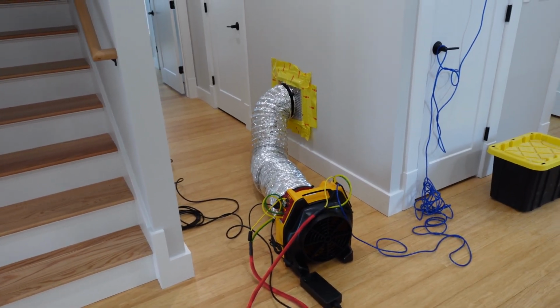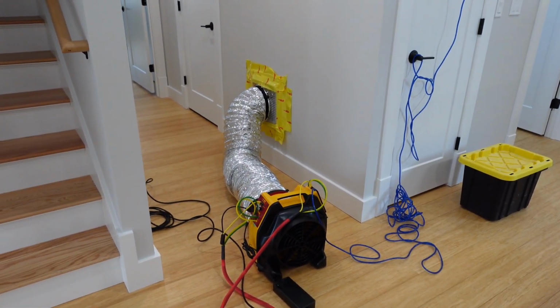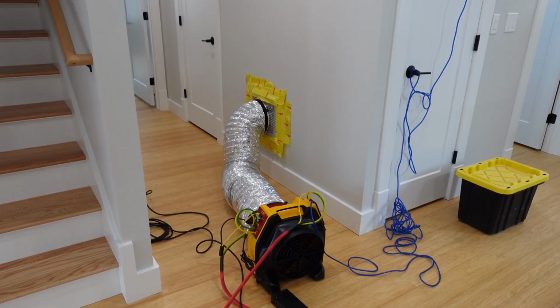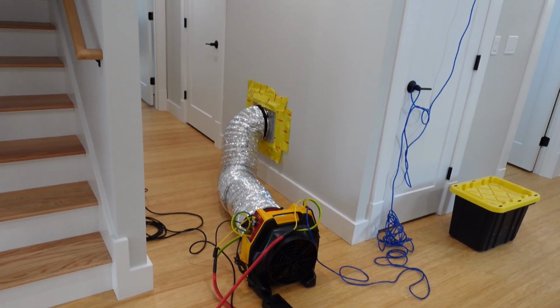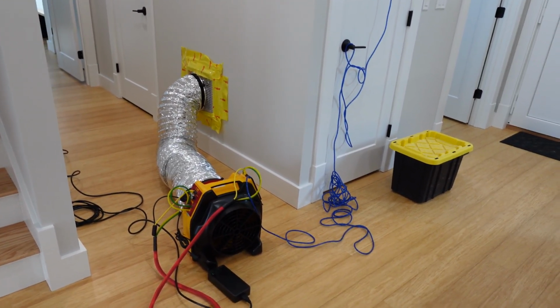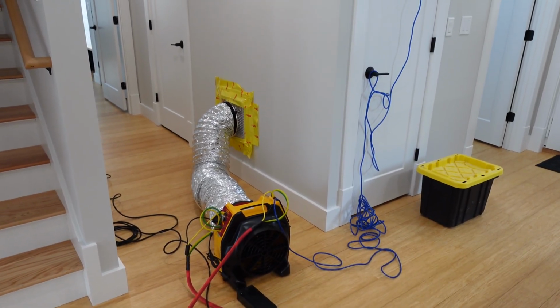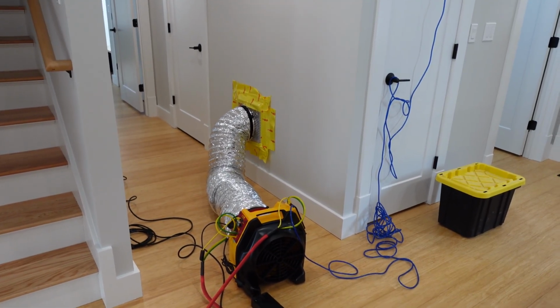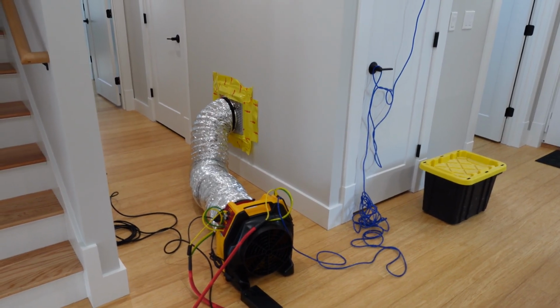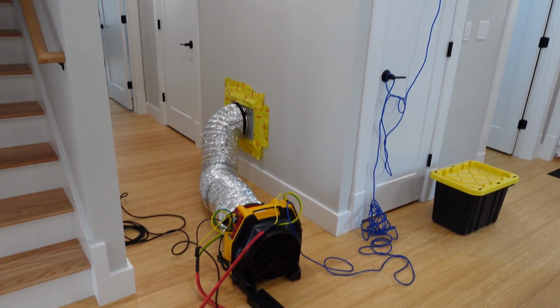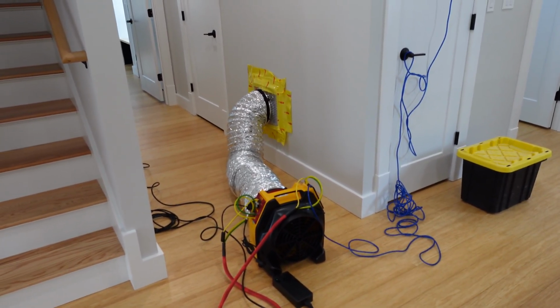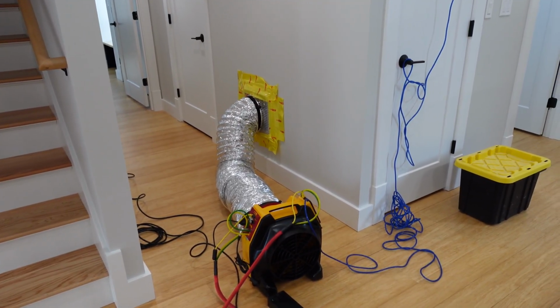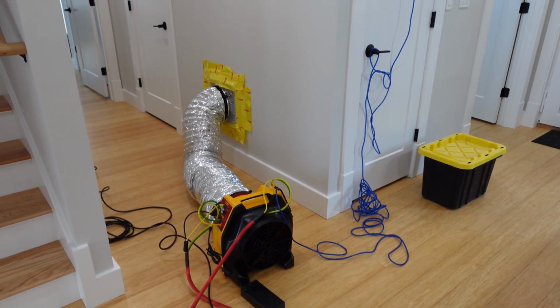Now let's talk about why you want to do a duct leakage test. So they are required anytime the ductwork is outside of the conditioned space, meaning insulated and heated or cooled. The reason why you want to do a duct leakage test is to ensure that the duct is tight and not leaking a bunch of conditioned air into unconditioned space. Obviously, you're going to lose a lot of energy that way. You could also be sucking in a lot of nasty stuff.